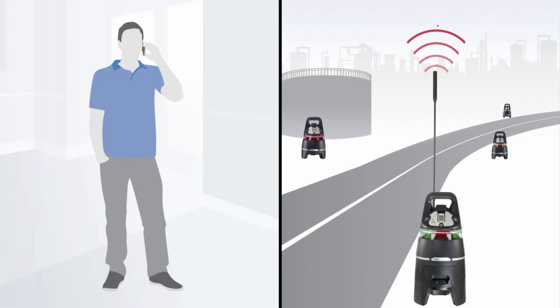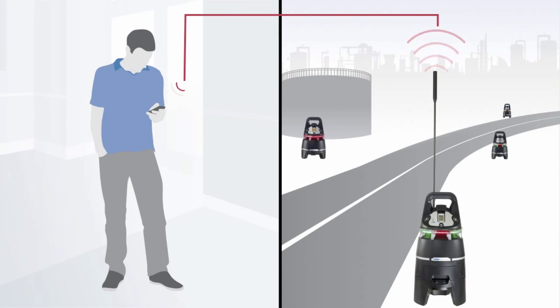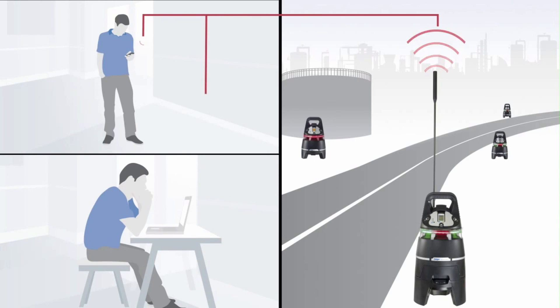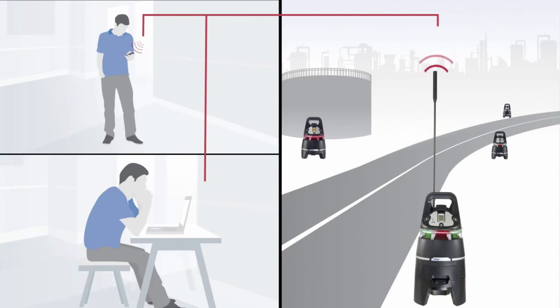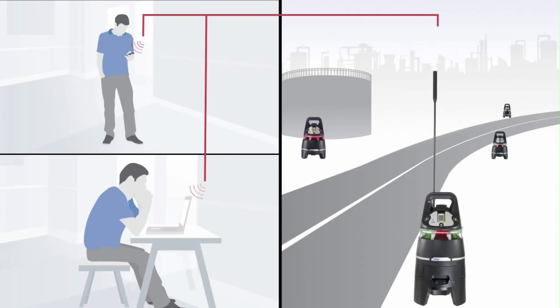The alarm can then be received, for example, on a mobile phone. The current gas concentrations and the GPS position can be called up via mobile phone, cloud, or PC at any time — not just when there is an alarm. It doesn't matter if one is 100 meters or 1,000 kilometers away. That saves time and personnel costs.